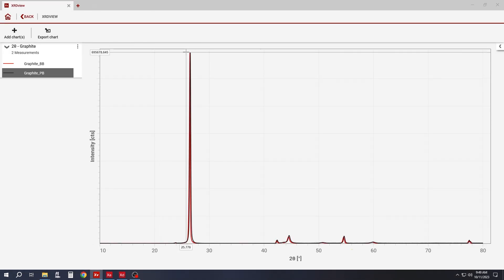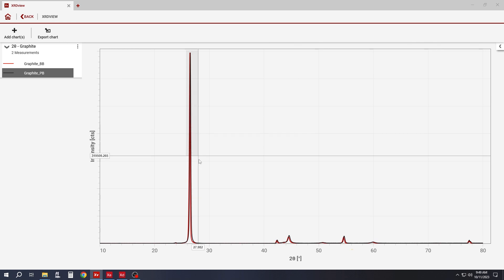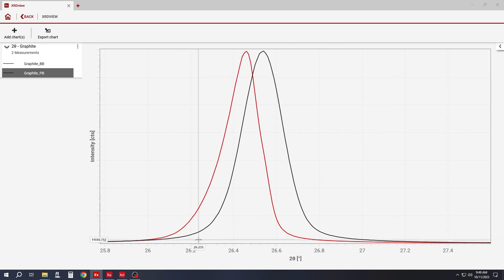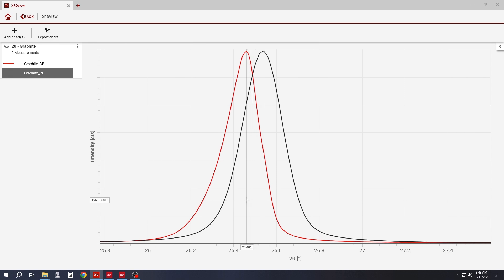The parallel beam mirrors are suitable for measurements of solid electrode powders as they compensate for possible peak shifts, which result from the X-rays penetrating too far into the sample. The peak position in the black curve, which is measured with parallel beam, is the correct 2-theta. However, the peak position in the red curve, measured with Bragg-Brentano geometry, is slightly shifted. Such shifts can be corrected by spiking the sample with a reference material with known peak positions.